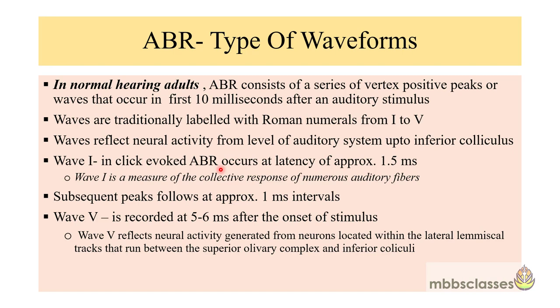The wave 1 in a click-induced ABR occurs at approximately a latency of 1.5 milliseconds, and the subsequent peaks occur at an interval of 1 millisecond. This means after a click-induced stimulus, wave 5 is recorded at approximately 5 to 6 milliseconds after the onset of the stimulus.